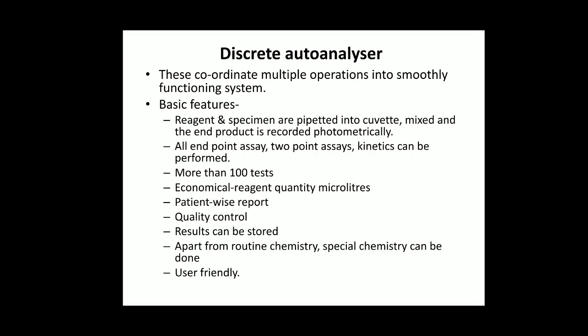Coming to discrete auto analyzers: this operates multiple programs in a smoothly functioning system. Basic features: reagent and specimens are pipetted into a cuvette, mixed, and the end product is recorded photometrically. All types of reactions — end point, two-point assay, kinetics — can be done. More than 100 tests can be done and it is economical. The analyzer is costly but the cost per test is less because the reagent volume used is very minimal — in microliters.